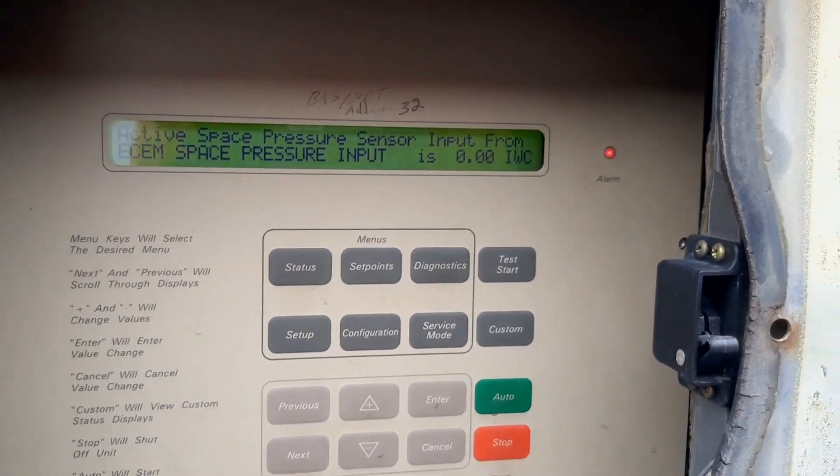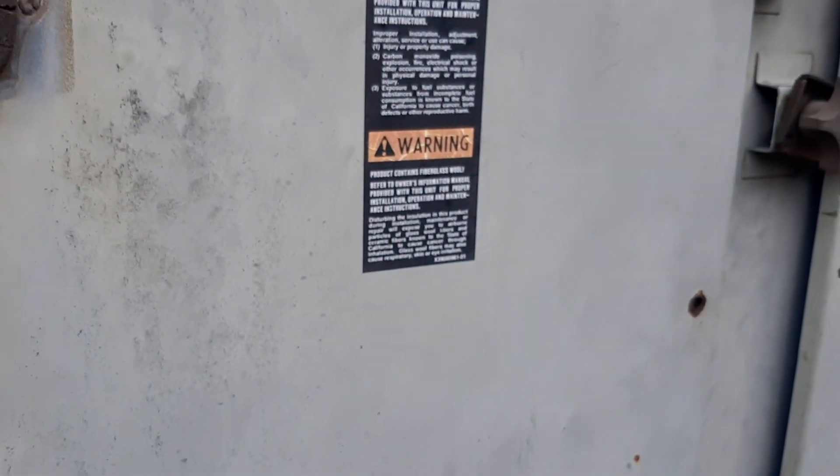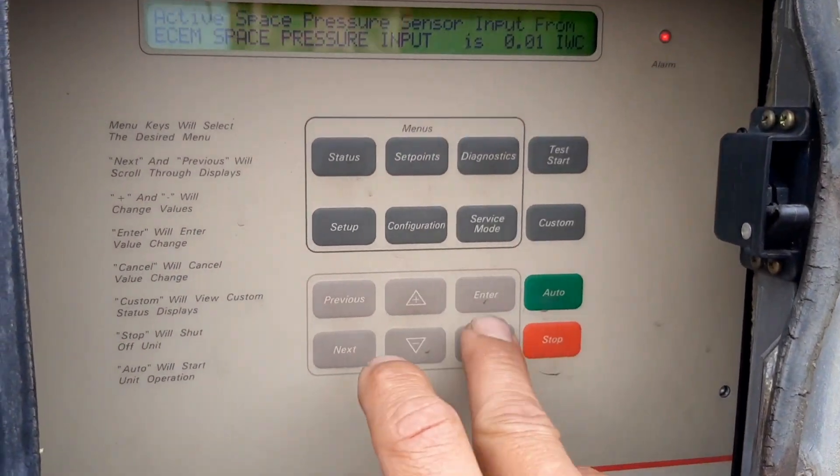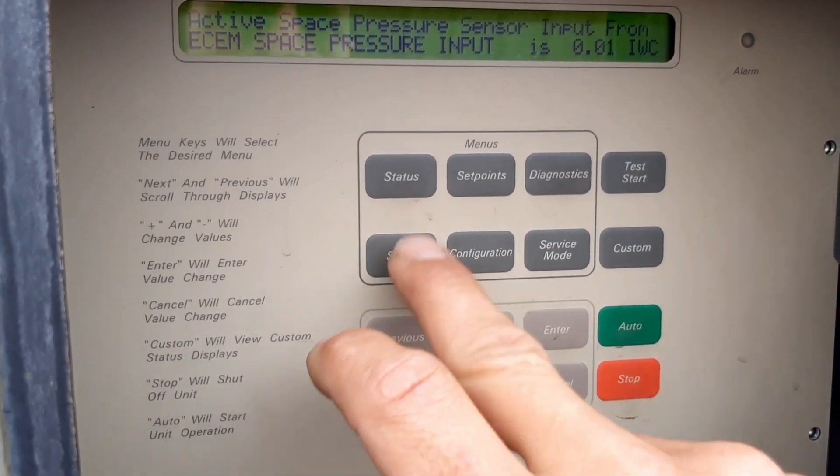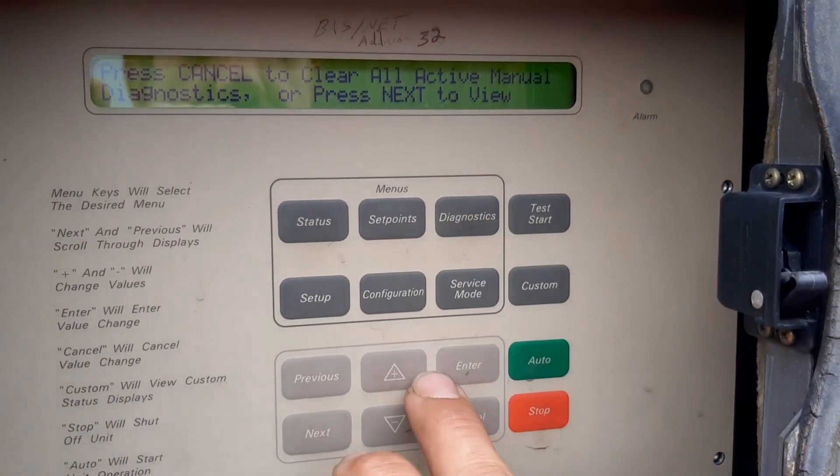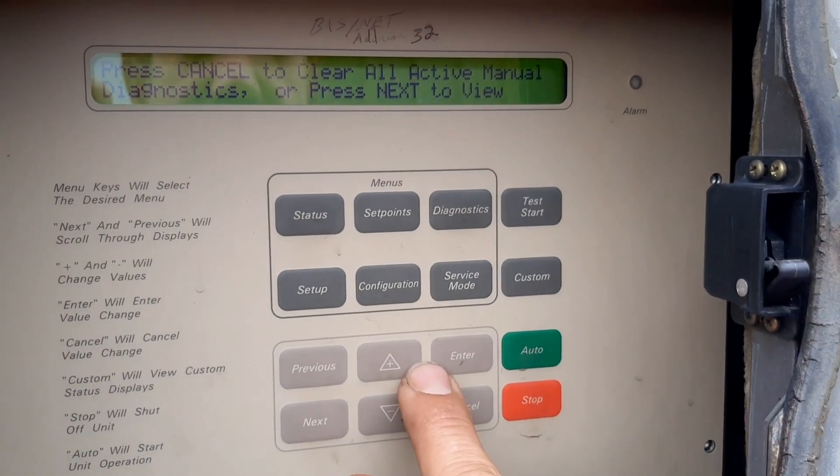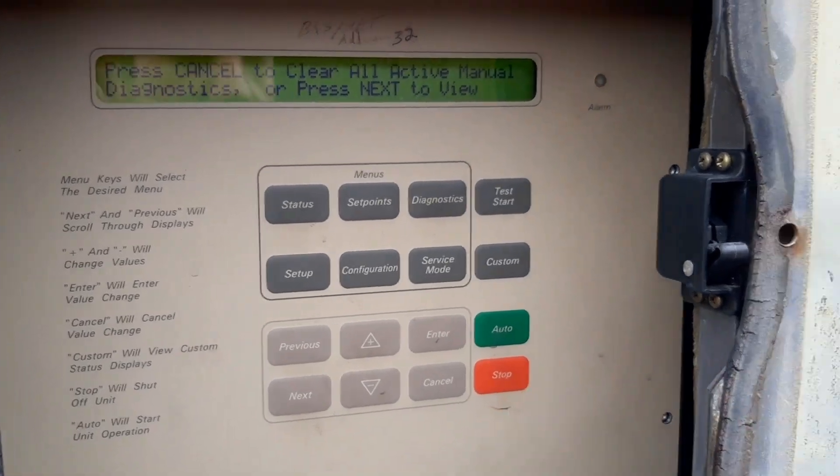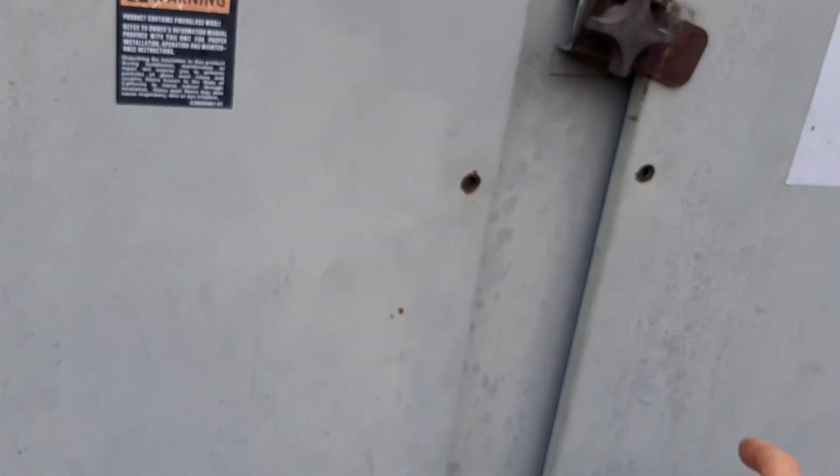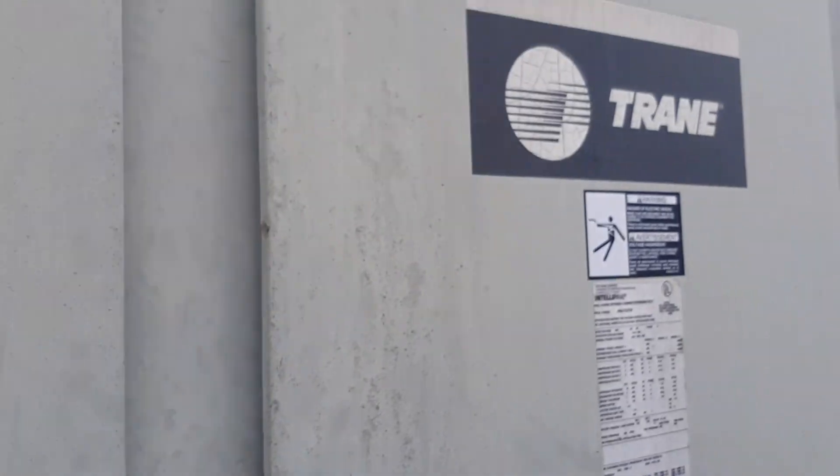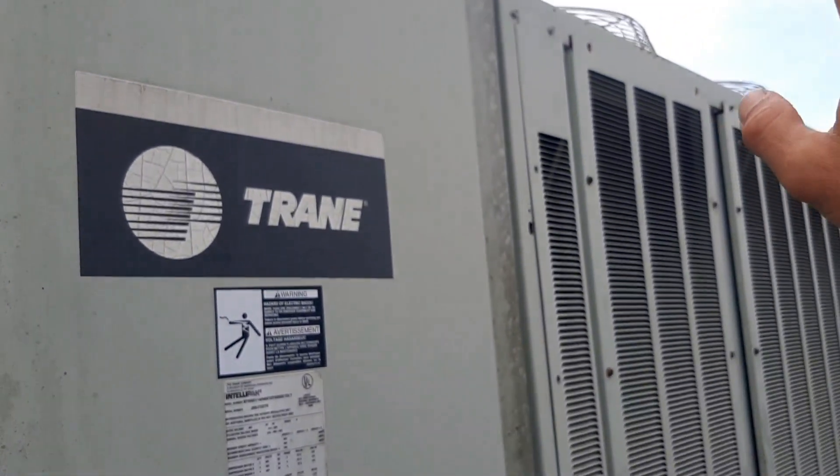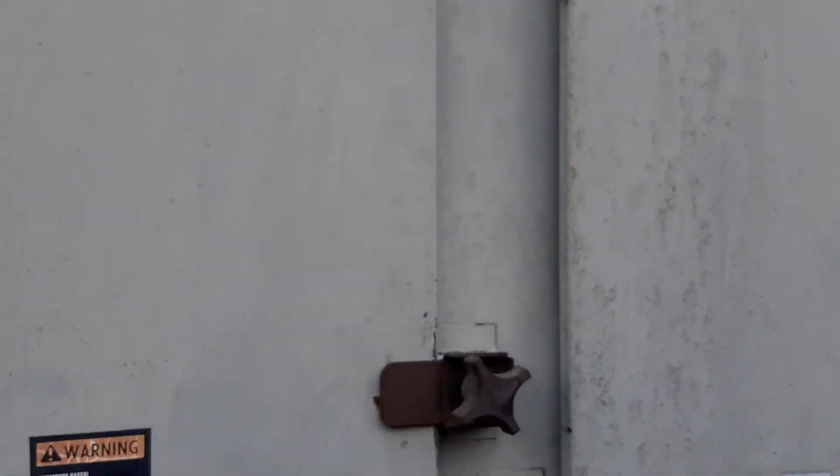Alright, well let's get these control panels open and look, see what we got. Let's go back to diagnostics. Before we clear those out, I want to look in here and see, make sure my contactors are pulled in, we'll get up top and make sure my fan motors are running.